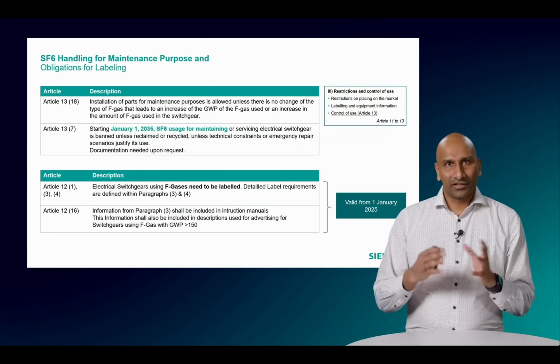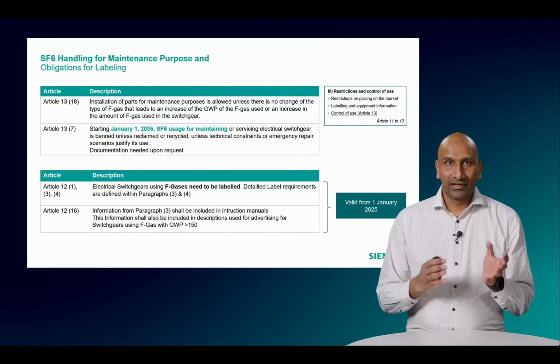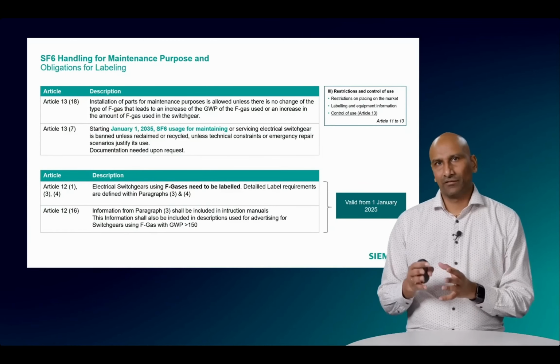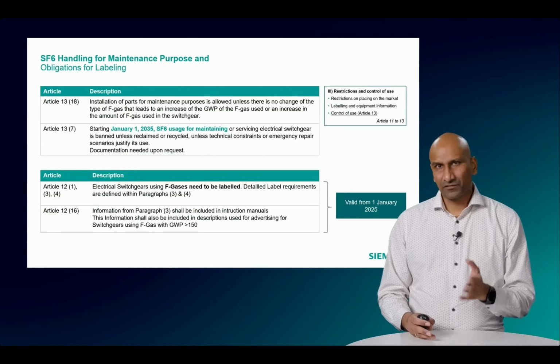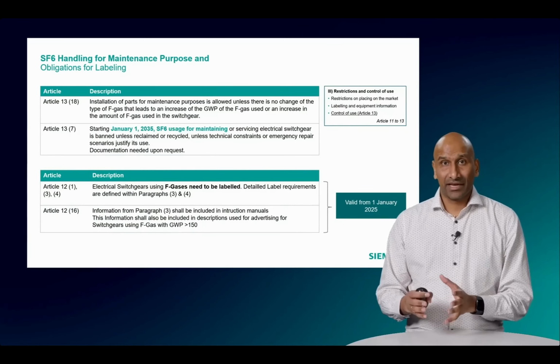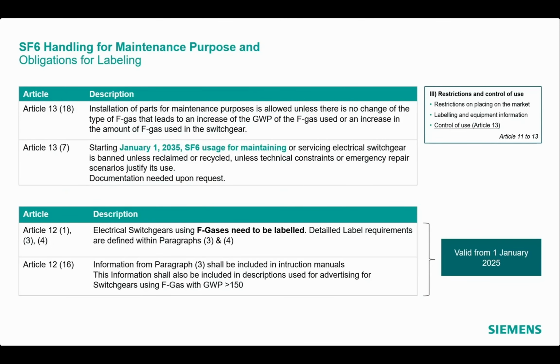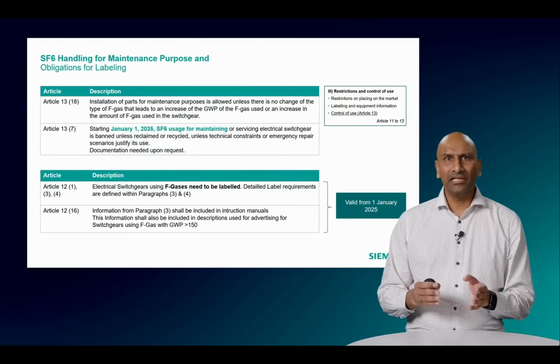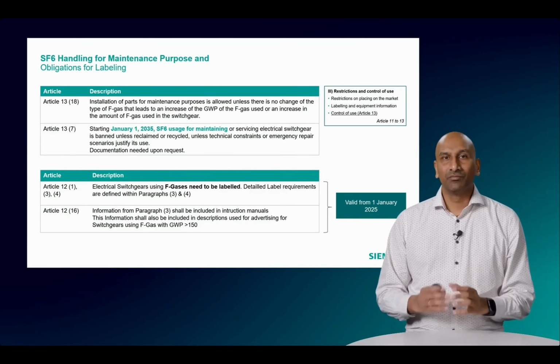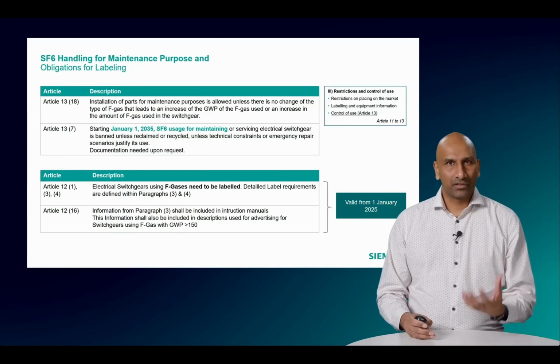Beyond the new installations, the regulation also imposes strict rules on maintenance of the existing SF6-based switchgear. From 1st of January 2035, the use of virgin SF6 gas for maintenance or service will be banned, and only reclaimed or recycled SF6 should be used. Documentation and reporting requirements will become mandatory to track the SF6 usage, ensuring full transparency and compliance. And from January 1st, 2025 onwards, any switchgear containing F-gases must be labeled, making it clear which equipment still relies on these greenhouse gases. I believe these measures highlight a clear message. The future is moving away from the F-gases, and companies need to start planning for this transition now.